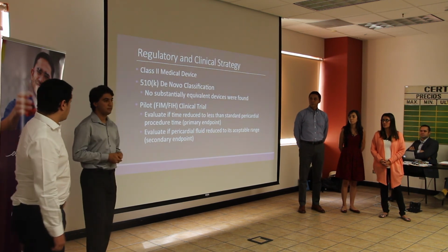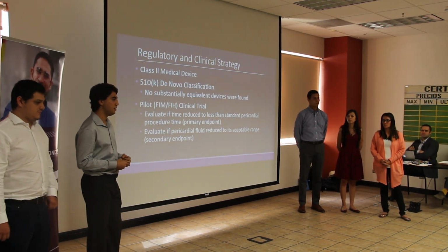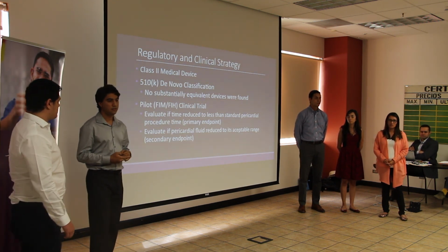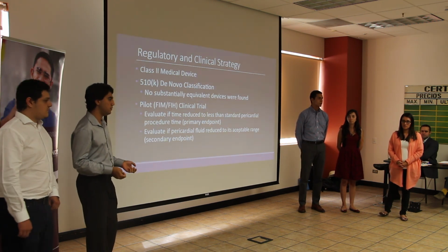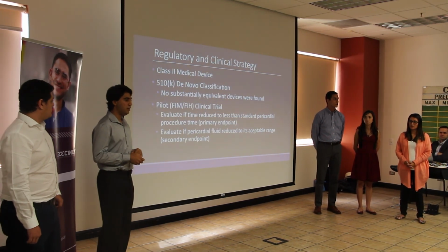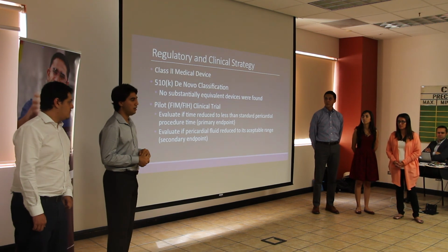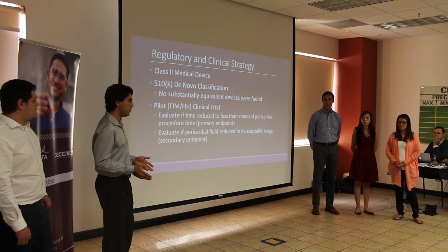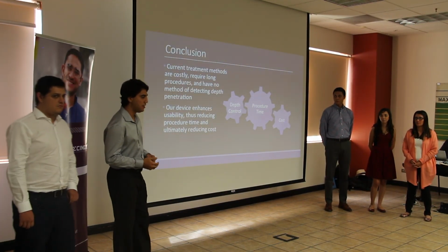Now, as a medical device, we have to follow the FDA regulations. First of all, they will classify us as a class 2 device, based on the classification of similar devices to the one we are designing. We cannot file for an exception because we didn't find a substantially equivalent device, so there's nothing to compare it with.